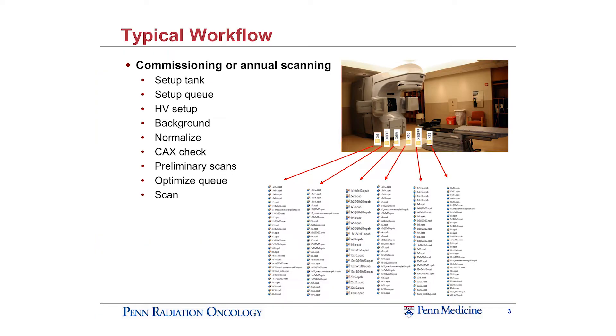When I set up the tank for either a commissioning machine or performing the annual scanning, there's your basic tank setup. I also have to find my scanning queue. We usually go through high voltage setup, we run the background, some normalization. We also do a CAX check to check the centering of our chamber. I also like to run some preliminary scans, usually in an energy that I'm familiar with, where I know what either the profile parameters should be or the PDD value should be for certain depths, just to check my setup and to get comfortable and know everything's okay before I go ahead and launch my scanning queue.